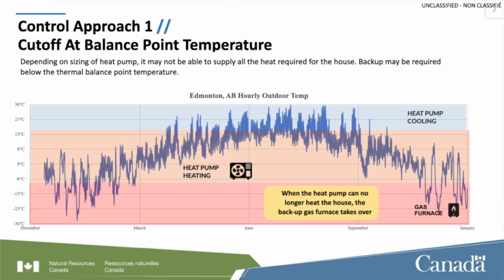Okay, the control approach one, cut off at the balance point temperature. That is what we calculated in the first F280 session. So what we're doing is cutting it off at minus 12.8 degrees. And what we can see from this graph is that the air source heat pump is covering an awful lot of the heating season. There's not a lot of time when you're actually running that supplemental. You can see a couple of days in January, a few days in February, December, November, and that's kind of normal. We talked about it in the last section, that 70% of the heating season is being covered by the air source heat pump. At least. I would think it's a little bit more in this case, just from looking at it.